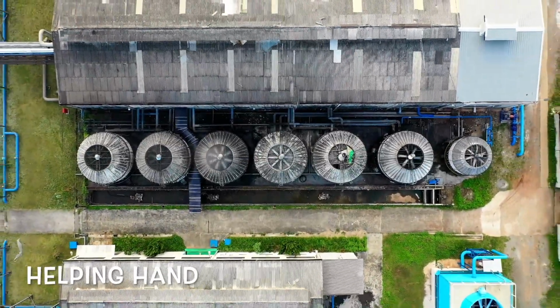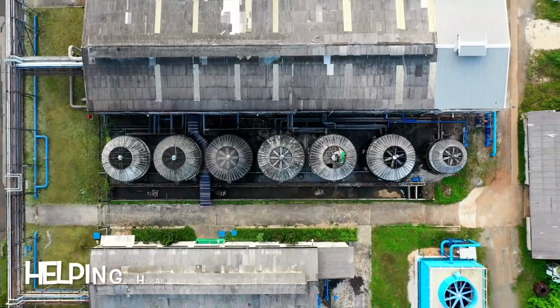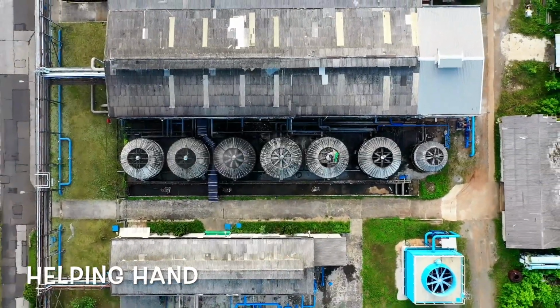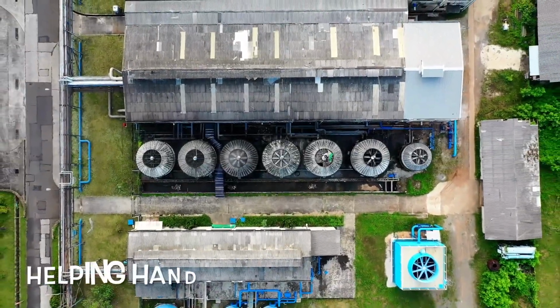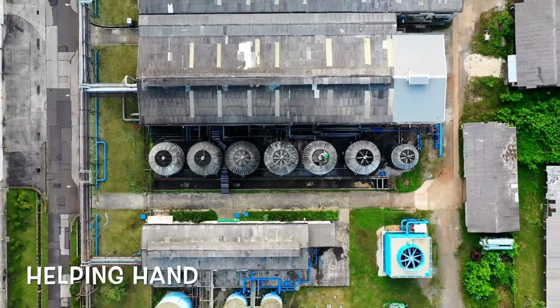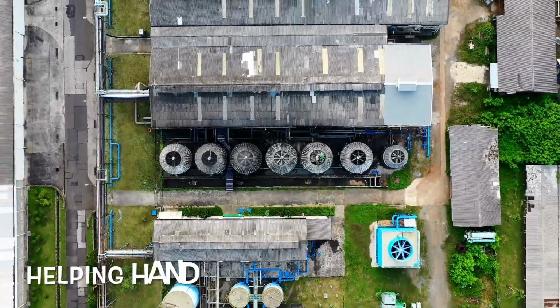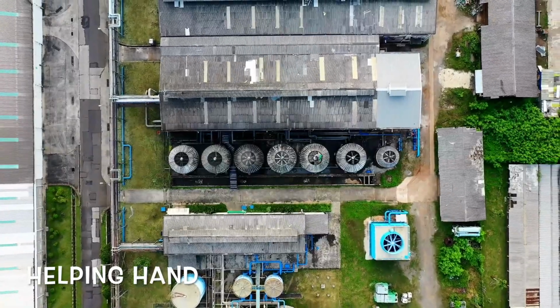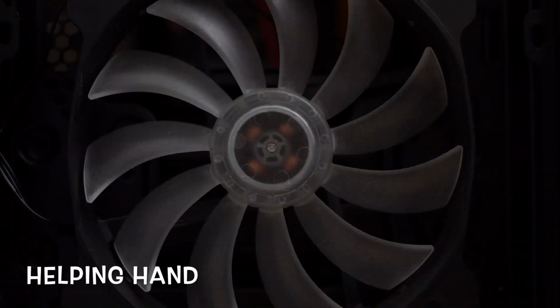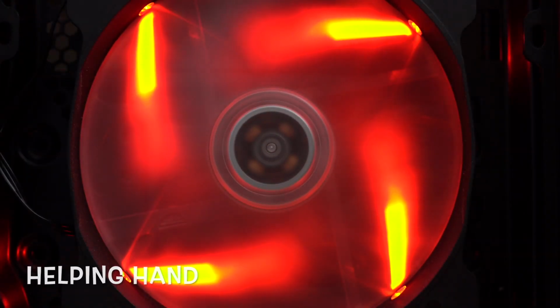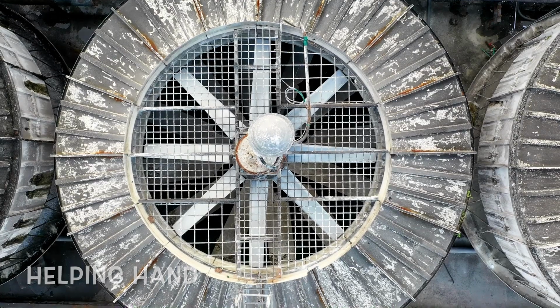Test the fan motor. If you've checked all the above steps and the fan still isn't working, there may be an issue with the motor itself. You can use a multimeter to test the continuity of the motor and determine if it's functioning correctly. If the motor is faulty, you might need to replace it.